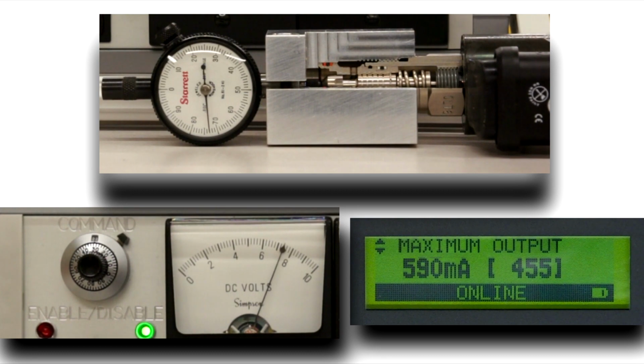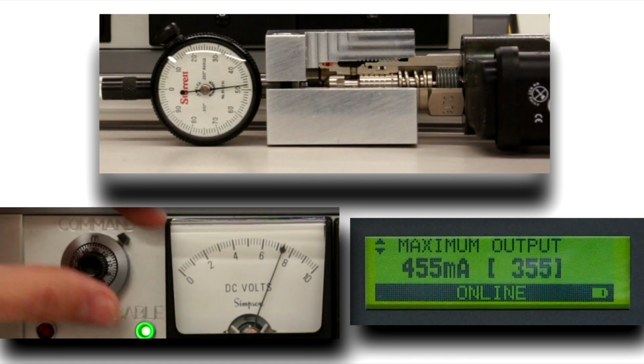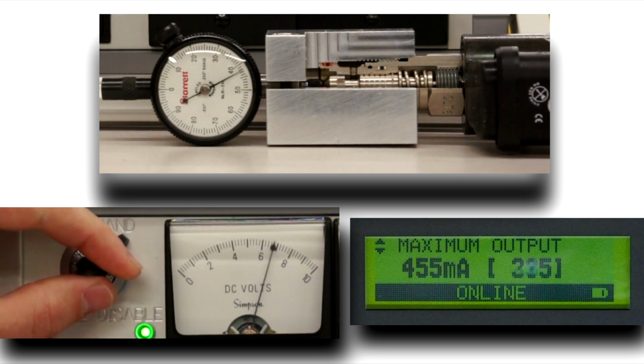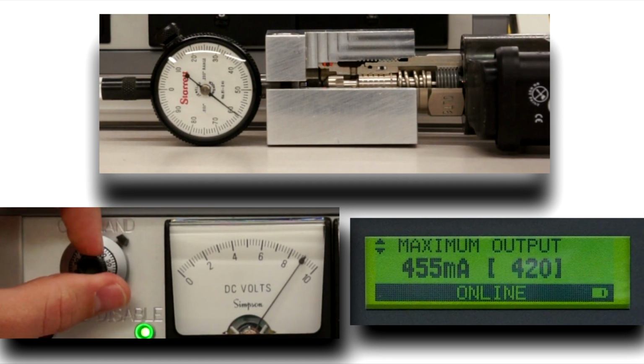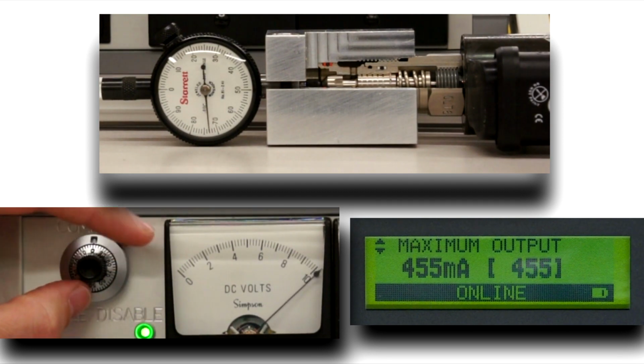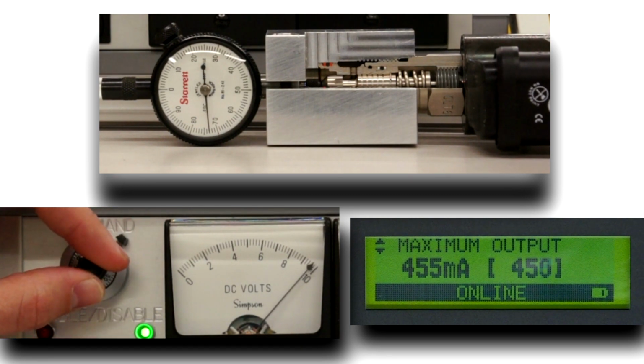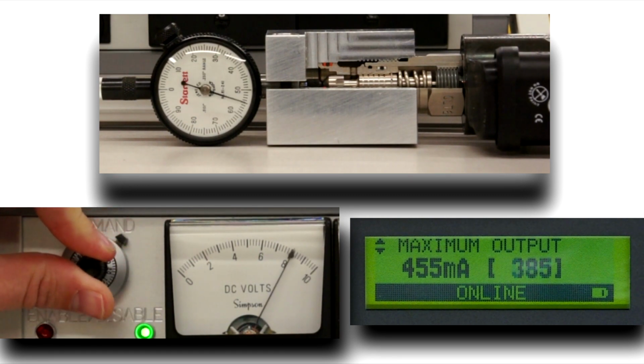Capture that value by hitting the green unlock button, and hit it again to lock it in. And now you have full control resolution so that you can go all the way to 10 volts input to get full stroke of the valve. Now you have complete proportional control of the valve in relation to your 0 to 10 volt input. We have now successfully tuned out the deadband.